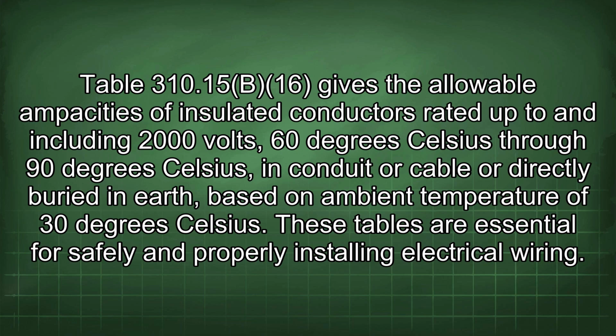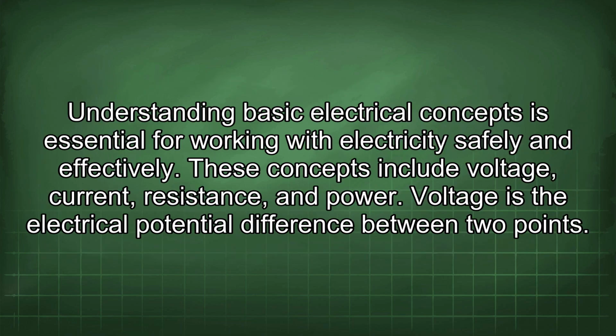Table 310.16 gives the allowable ampacities of insulated conductors rated up to and including 2000 volts, 60 degrees Celsius through 90 degrees Celsius, in conduit or cable or directly buried in earth, based on an ambient temperature of 30 degrees Celsius. These tables are essential for safely and properly installing electrical wiring. Understanding basic electrical concepts is essential for working with electricity safely and effectively.